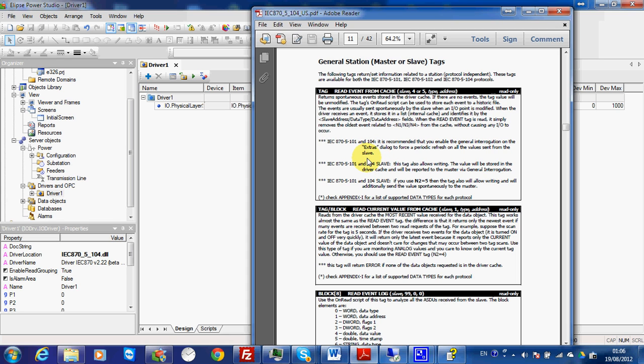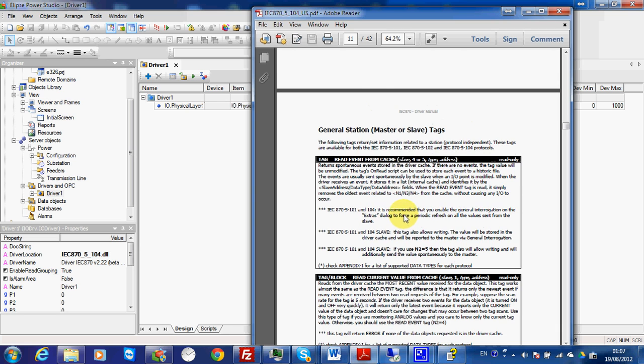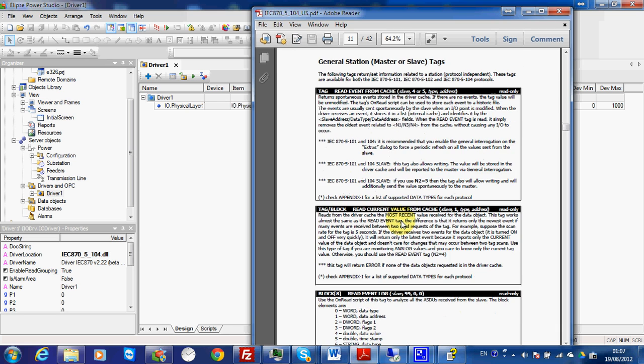N1 will be 1 because my slave address is 1. For the function, I will use 'read event from cache,' which is the value 5. So N2 is 5, and this is for reading from the IEC 104 slave.